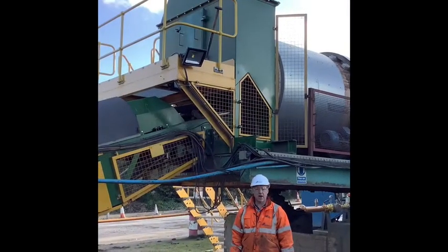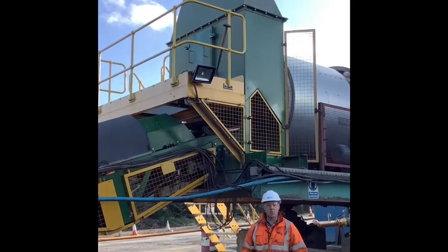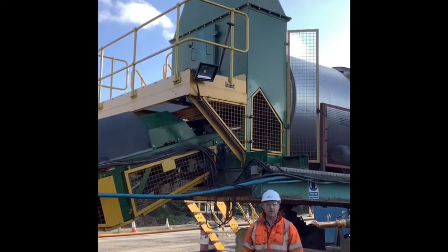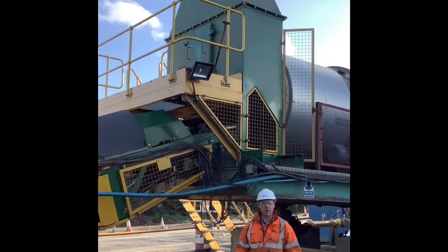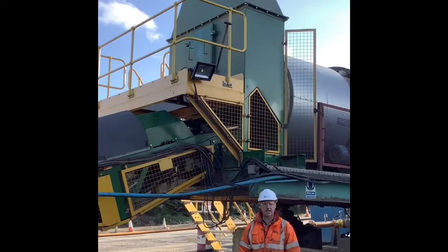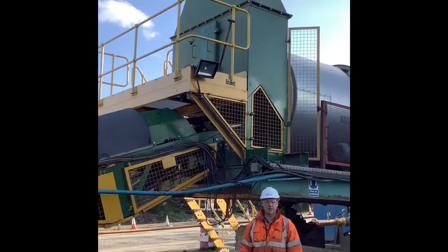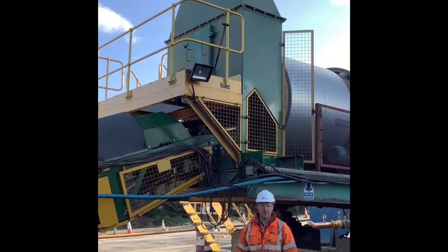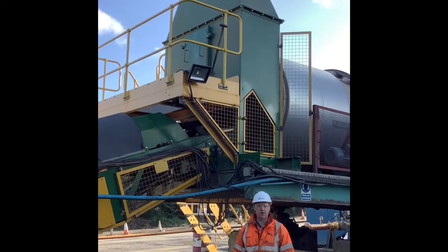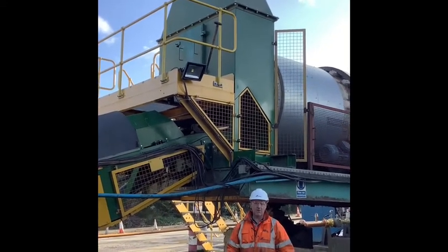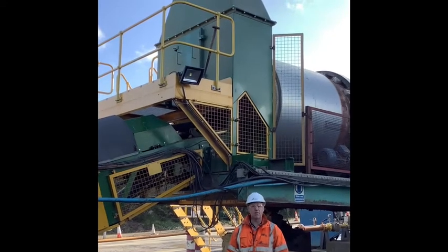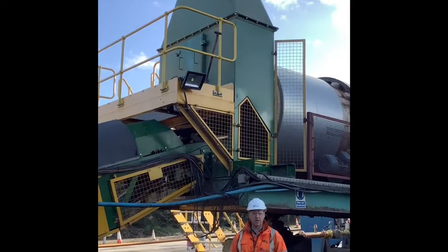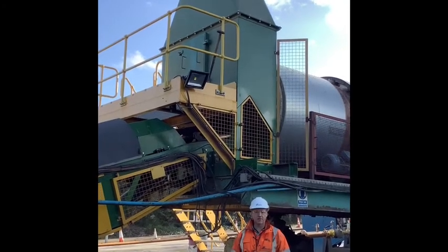Something else to consider about your extraction system, particularly in wet winter time, is the blocking up with wet aggregate of the feed end of your dryer. If it blocks that end up, which you'll see a photograph of shortly, it will affect the ability of the extraction system to take air off to go to the baghouse. This will adversely affect the performance of the cleaning of your baghouse mechanism. We've had 3 occasions so far this year where we've had to go inside the dryer and clean out the feed end because it's been completely blocked up with wet aggregate from our own quarries.